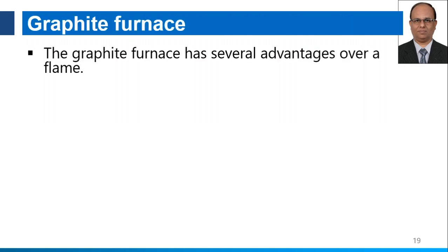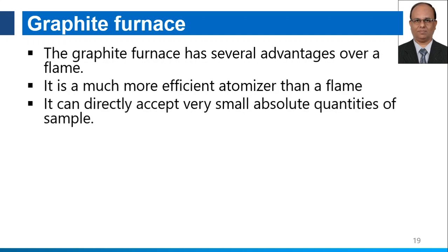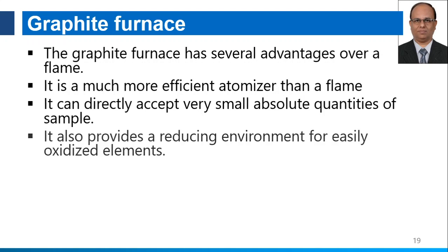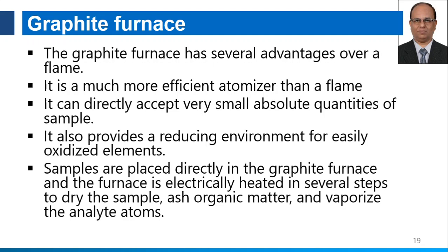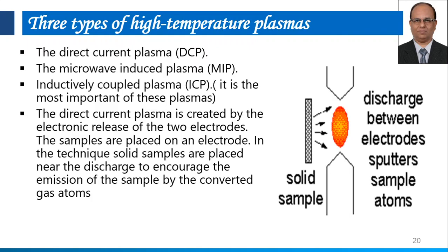I will explain the graphite furnace in detail. The graphite furnace has several advantages over the flame — it is a much more efficient atomizer. It can directly accept very small absolute quantities of sample; we don't need to prepare solutions. It also provides a reducing environment for easily oxidized elements. Samples are placed directly into the graphite furnace and the furnace is electrically heated in several steps to dry the samples, ash organic matter, and vaporize the analyte. A modified form of atomic absorption spectroscopy also uses plasma discharge techniques.